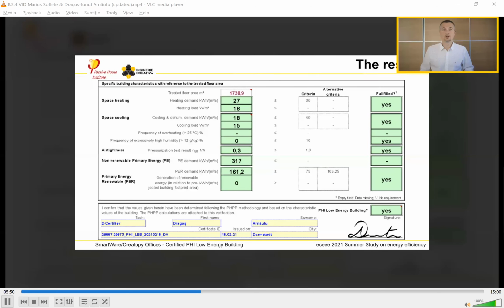The heating demand is 27 kilowatt hours per square meter per year. The heating load is 18 watts per square meter. The cooling demand is 18 kilowatt hours per square meter per year, while the cooling load is 15 watts per square meter. The air tightness was measured at 0.3 air changes per hour at an under and over pressure of 50 pascals, which is great, and it is proof of great workmanship and attention to detail.